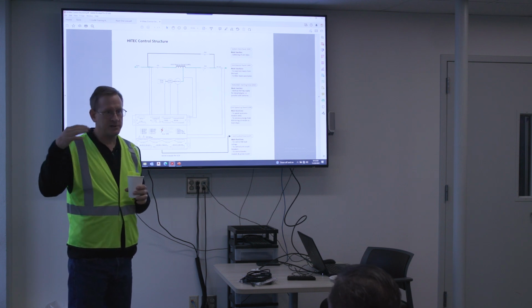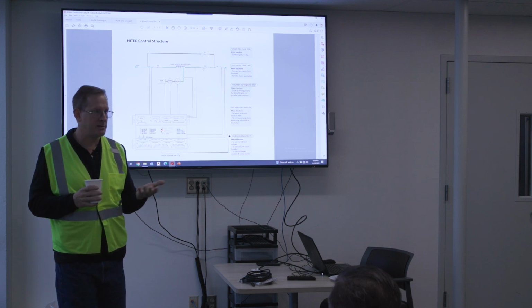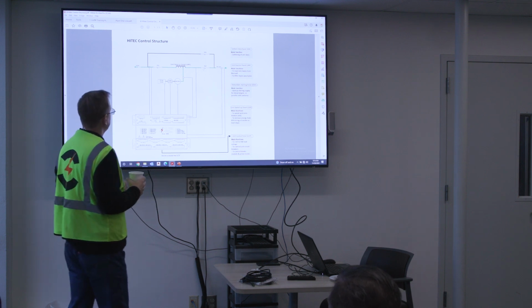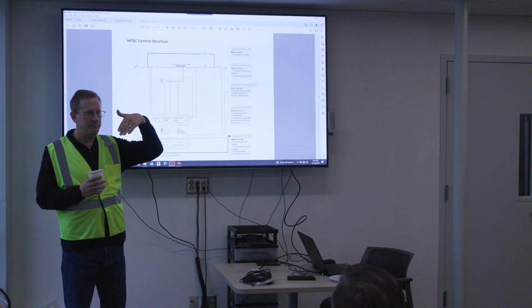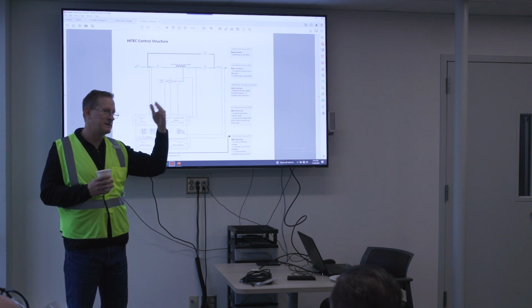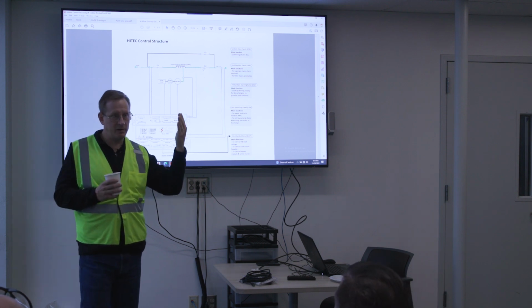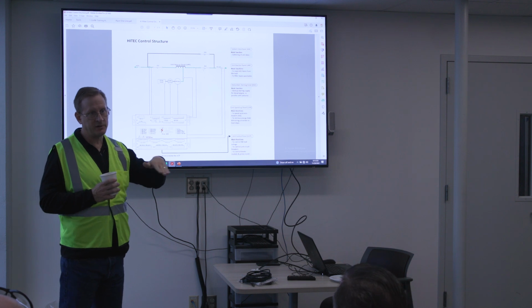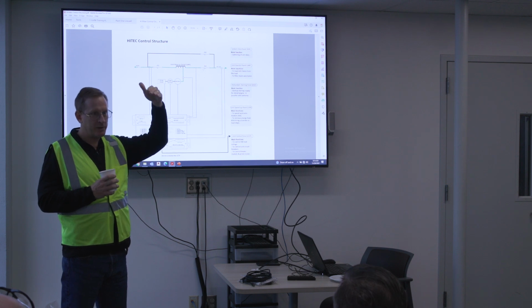And we do that for certain functions like paralleling, for load sharing, for kVAR sharing, for paralleling machines. And I think we can also use that because sometimes the utility voltage may not be right at 4160. Sometimes it'll be a little bit lower, sometimes a little bit higher. I've noticed on your site, I think during testing last week, we come in the morning and your utility voltage would be 4100 maybe, and then later in the day it'd jump up to 4180 or something.